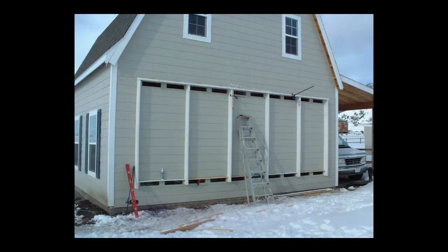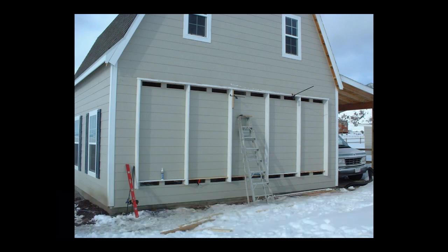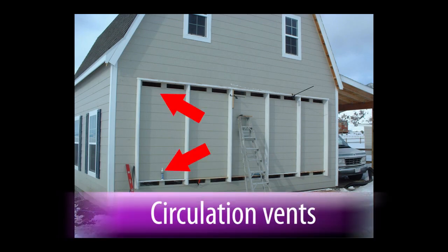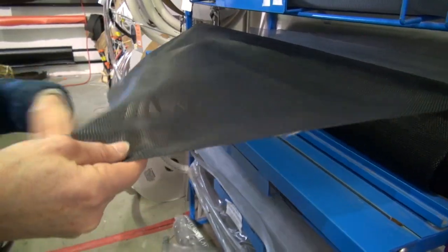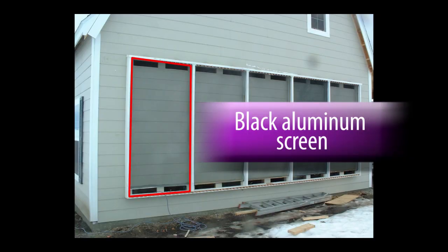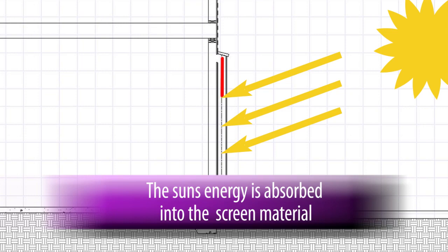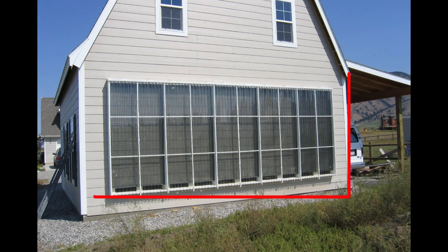This collector is a series of four-foot-wide, two-by-six frames attached to the side of the building. A series of vents are cut through the wall into the building at both the top and bottom of each frame. Within each two-by-six frame, common black aluminum window screen material is suspended. This black aluminum screen acts as an absorber to capture the heat energy from the sun. Clear corrugated polycarbonate panels cover the frame and screen to provide an airtight exterior seal.